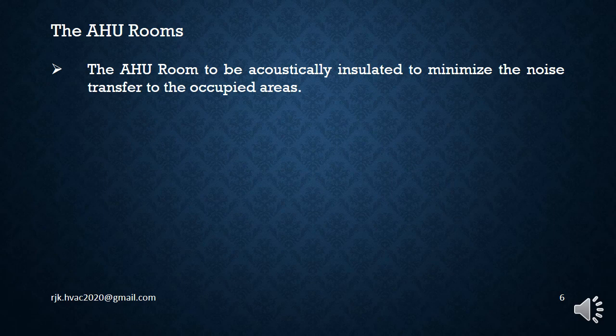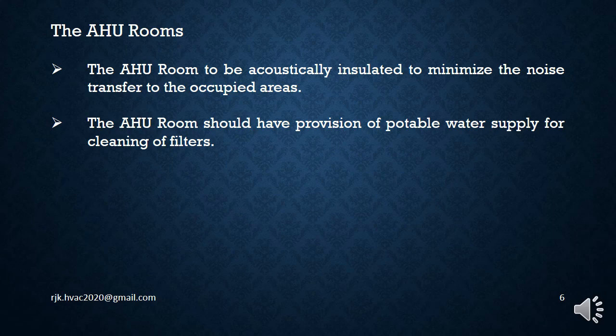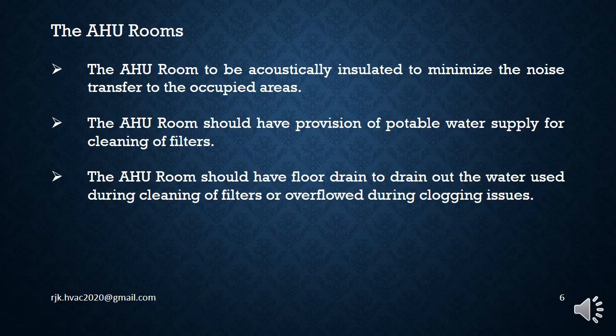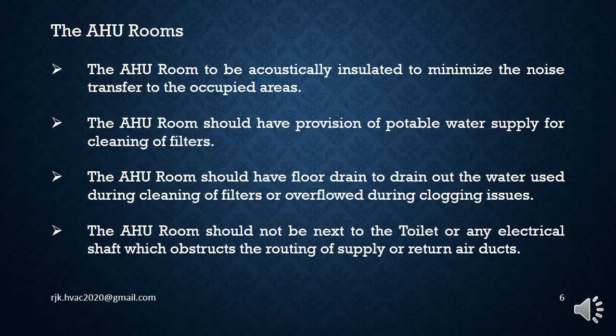The AHU room to be acoustically insulated to minimize the noise transfer to the occupied areas. The AHU room should have provision of potable water supply for cleaning of filters. The AHU room should have floor drains to drain out the water used during cleaning of filters or overflowed during clogging issues. The AHU room should not be next to the toilet or an electrical shaft which obstructs the routing of the supply or return duct.